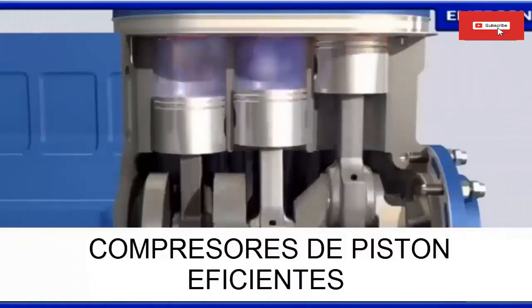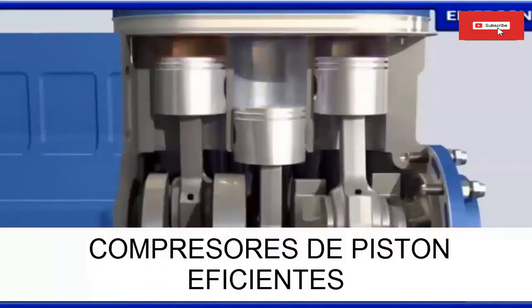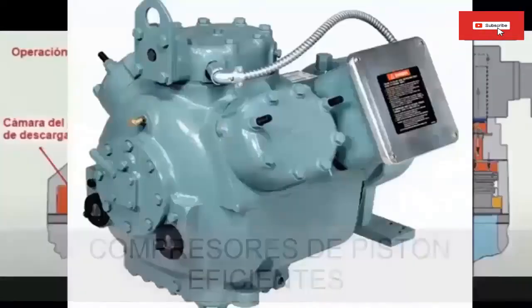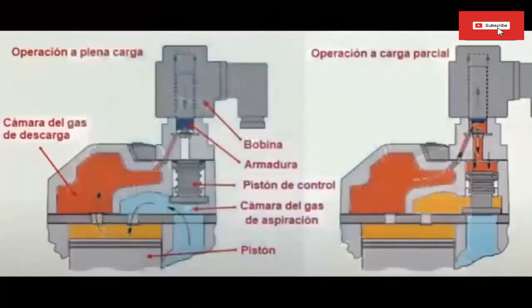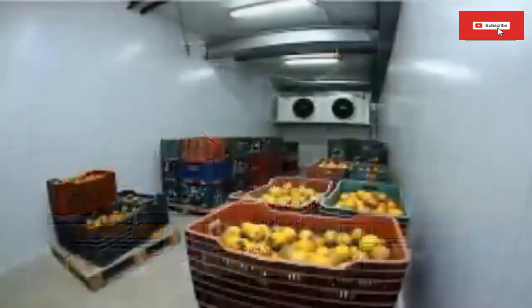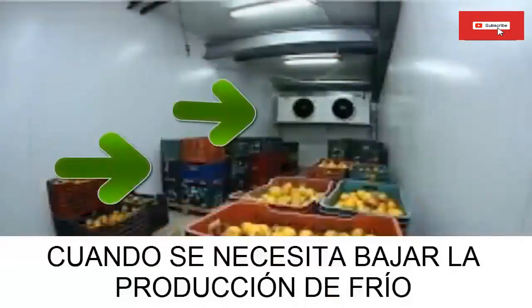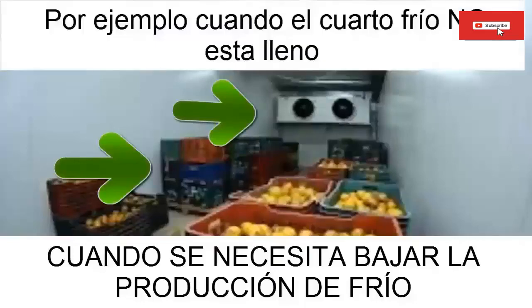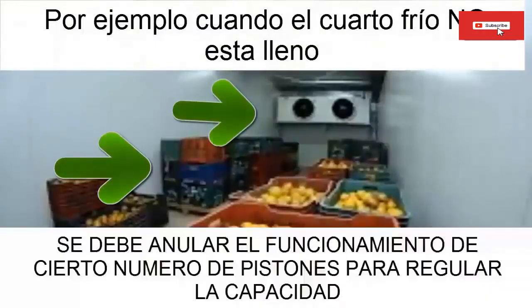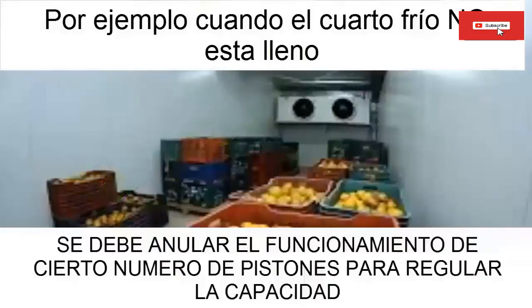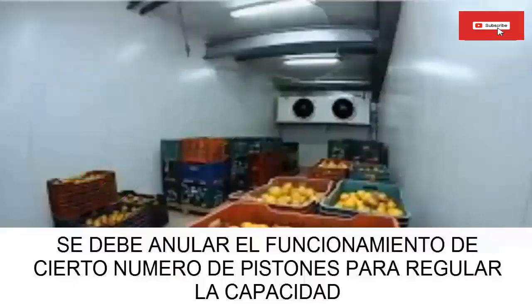Piston compressor capacity control in refrigeration and air conditioning with unloaders. 1. When the operating conditions of the refrigeration or air conditioning system are not so severe, that is, when the cooling load is lower than the design load, or the outdoor environment temperature is low, then at that time it is necessary to regulate the capacity of the piston compressor.